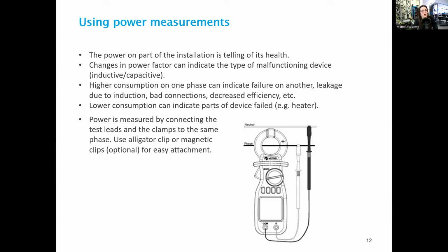Then we can look at power losses caused by leakage current. Particularly if we have inductive leakage, this can cause quite high power losses. Higher consumption can also indicate problems like problems with connections or weakened connections, aging equipment with lower efficiency, and similar. If we find lower consumption in parts of the installation, it tends to point to a whole device failing so that it doesn't draw any power any longer.